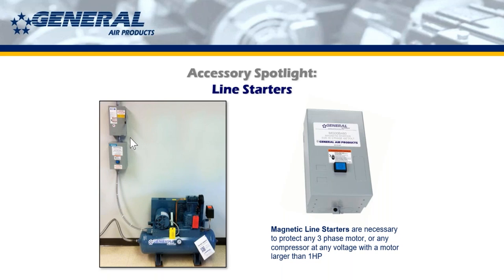A lot of times this happens when electricians are rewiring a building or rewiring a section of a building, and potentially the compressor gets put on a circuit with other equipment, things like that, because it should be on a dedicated circuit. So it can happen like that, where things are just being changed from the original design, and then all of a sudden it gets bad voltage, whether it's low voltage or high voltage, depending on what it's been pre-wired for. You need to go out there and reset it, and then it'll come back on.